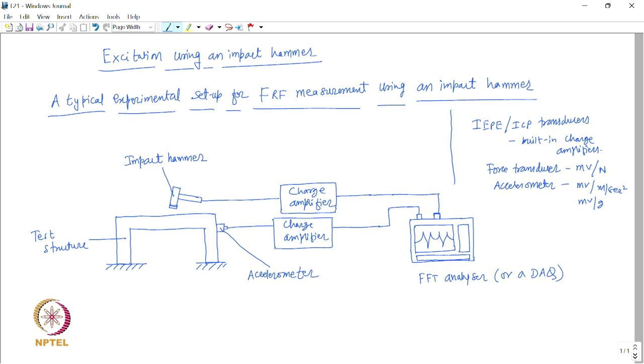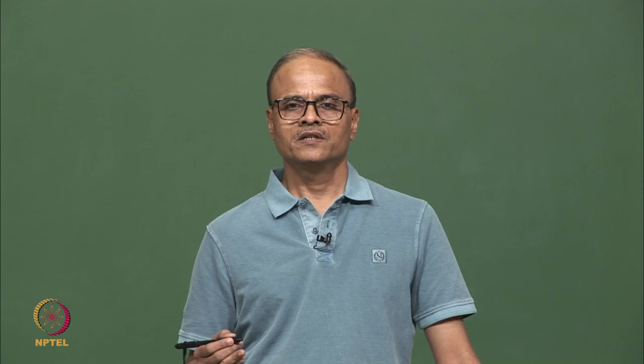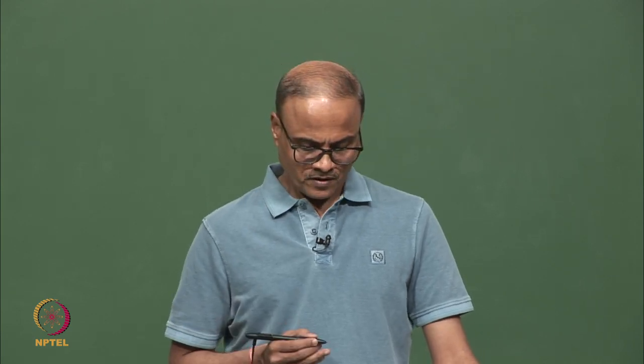If the sensors are of charge type, the force transducer sensitivity would be in terms of picocoulombs per Newton, and the accelerometer sensitivity in picocoulombs per meter per second squared or picocoulombs per g of acceleration. In either case, what we get in the FFT analyzer are voltage signals which are proportional to the force and acceleration signals.